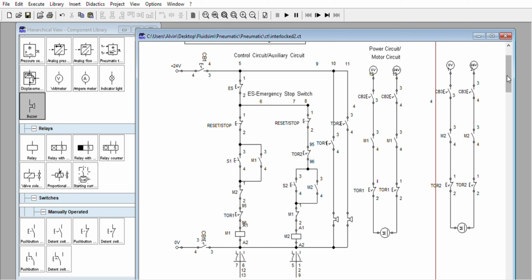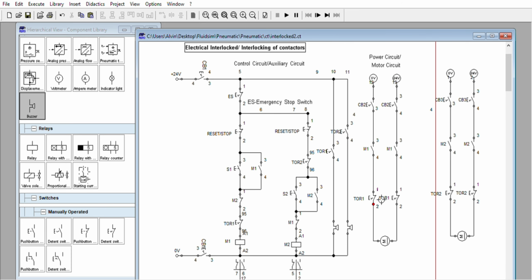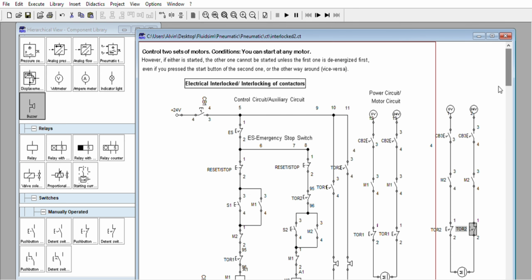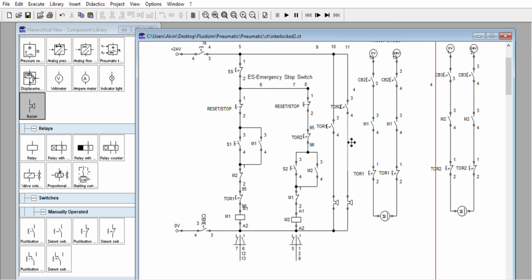So in this case, if the motors are not identical, so you have 2 different sizes of overload relay, 2 different sizes of circuit breakers. You can have circuit breaker main here. Based on your local electrical code, you can connect them here. Connect. This will become the main. These 2 are the branches. Calculated based on the current, full load current of the motor.